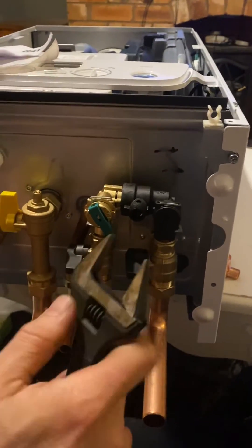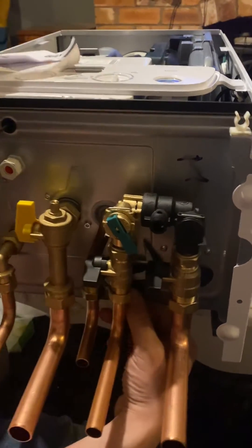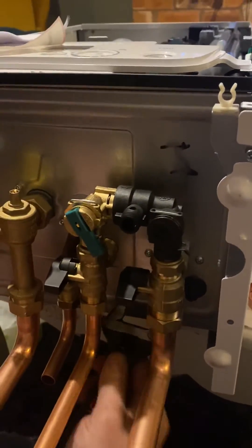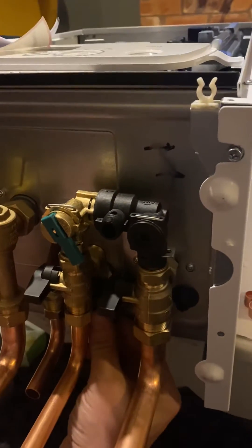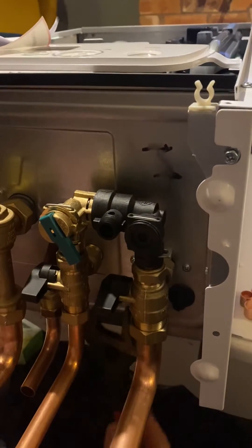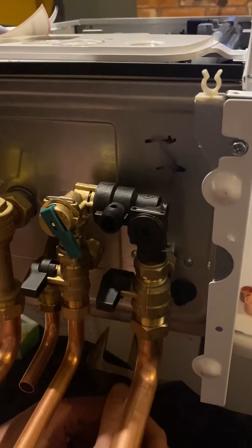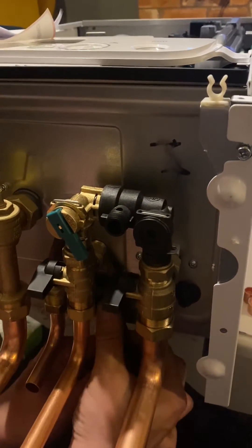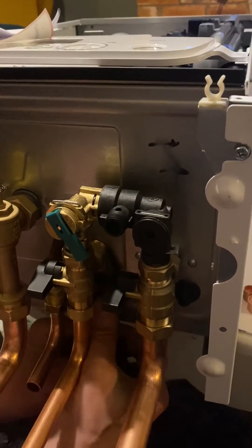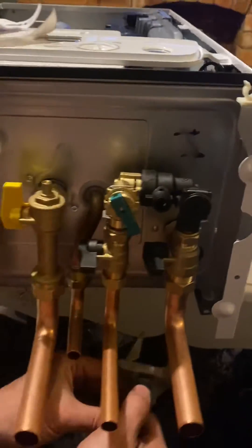There's a good chance it's best to do this while you're here. If you pipe them up the night before like I tend to do, there's a chance you've disturbed these at the back, so when you actually hang the unit it can be quite difficult to tighten the back up again. Just nip them up now — if you haven't nipped them up before you stick it on the wall, you'll have to take the filling loop off again just to get to it.